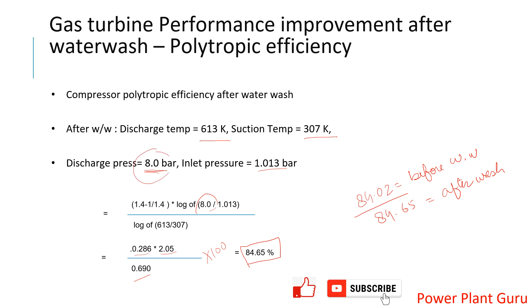The improvement can also be seen in the discharge pressure: it went from 7.86 bar before water wash to 8.0 bar after. When compressor efficiency improves, the work done by the compressor for the same energy input is reduced. For example, if the turbine produces 100 megawatts and the compressor was consuming 65 megawatts, with improved efficiency it might consume only 62–63 megawatts, saving 1–2 megawatts. This video describes the concept of water wash and how to assess its effectiveness using polytropic efficiency. Thank you for watching.